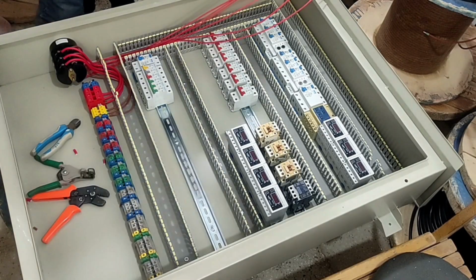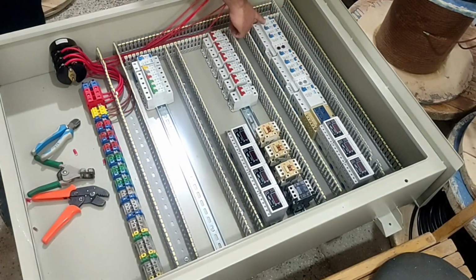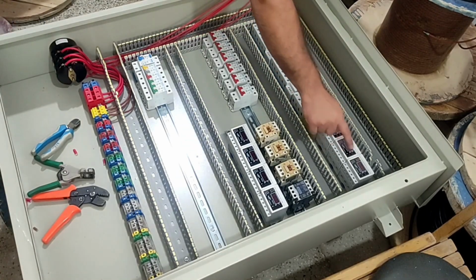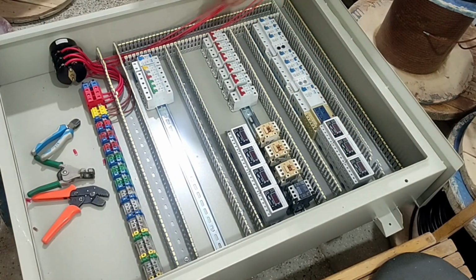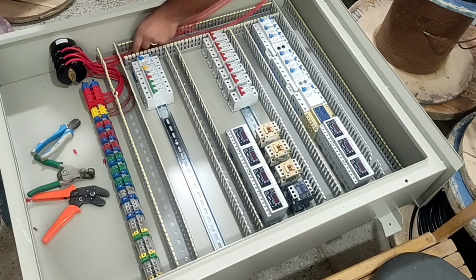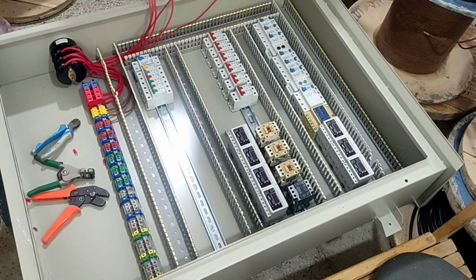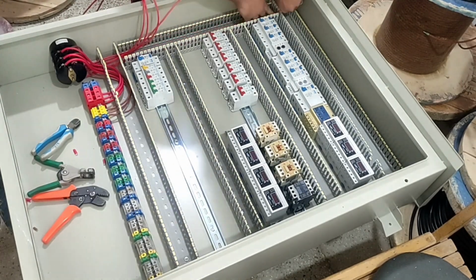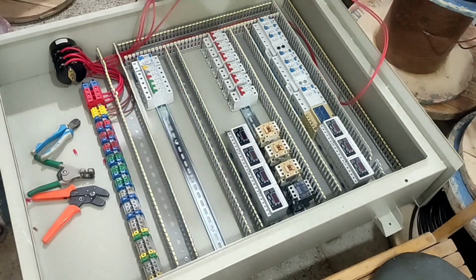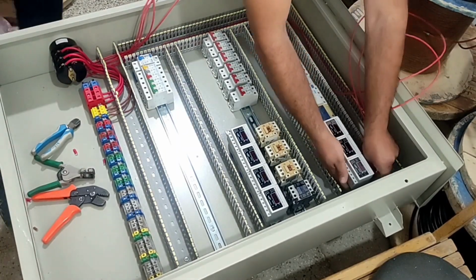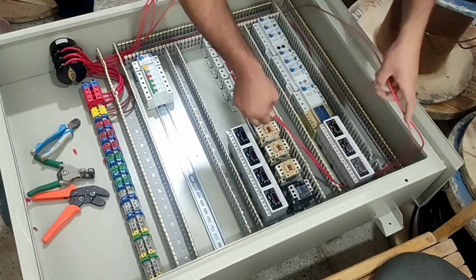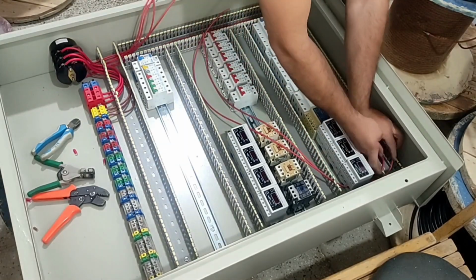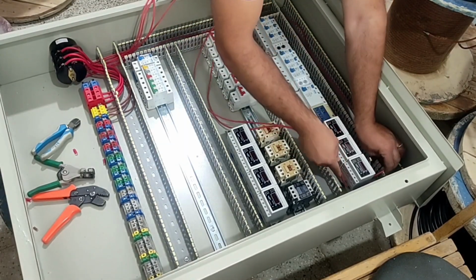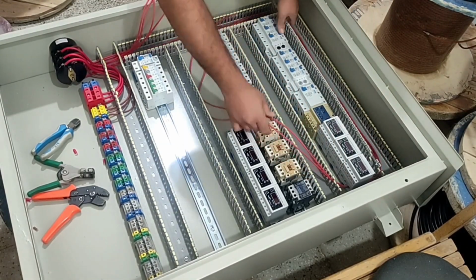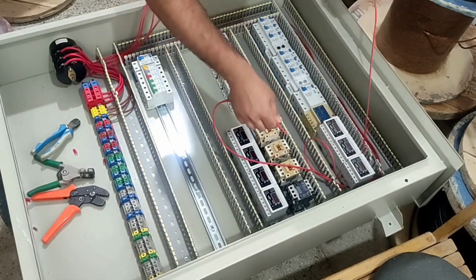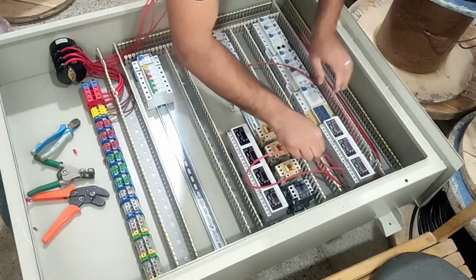Now we connect the three-phase outputs to the single-phase RCCB switches. We do this in such a way that the phase division is as symmetrical as possible. That is, we connect each phase to two RCCB switches. As you can see in the picture, before connecting the wires to the RCCB switches, we pass them through the hole of the current controller so that the current passing through each phase is specified and displayed.